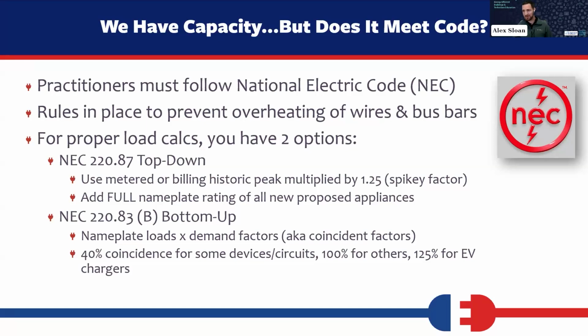There are whole other presentations on this, but we have two options to meet the National Electric Code requirements. There's a top-down method where we look at the previous 12 months of billing data or metered usage, do a little bit of math, multiply it by 1.25, and then add in the nameplate rating of all new proposed appliances to see whether or not we can successfully install those appliances on an existing panel. That's one method, but it's pretty rare.